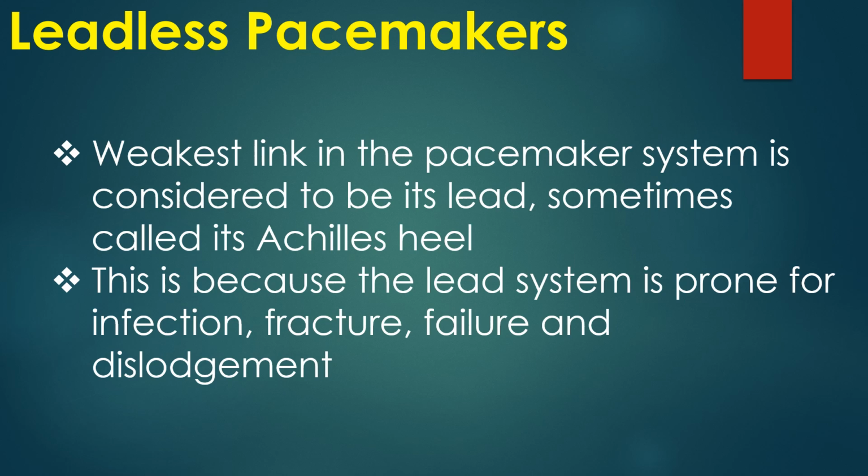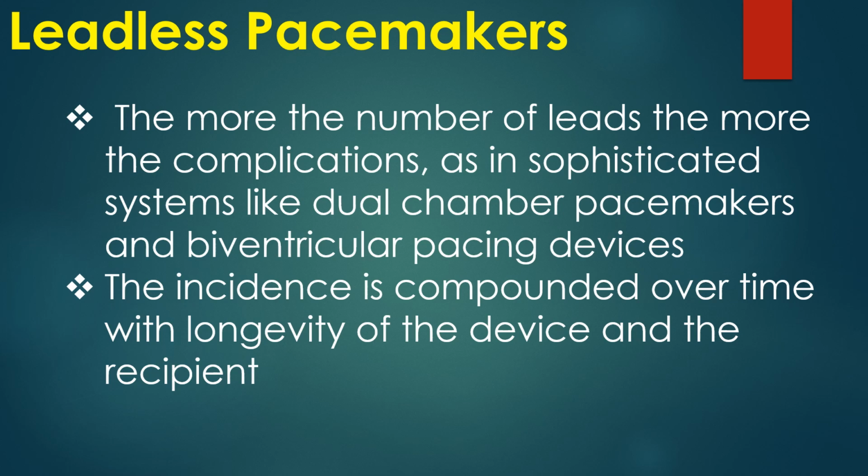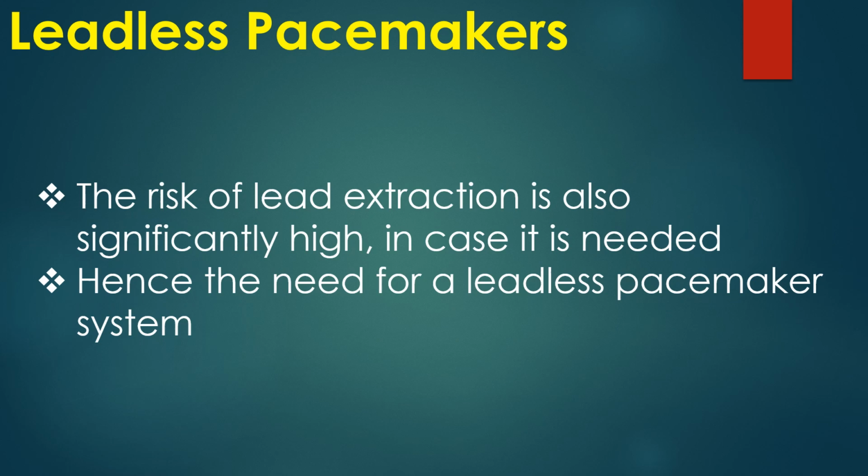Weakest link in the pacemaker system is considered to be its lead, sometimes called its Achilles heel. This is because the lead system is prone for infection, fracture, failure and dislodgement. The more the number of the leads, the more the complications, as in sophisticated systems like dual chamber pacemakers and biventricular pacing devices. The incidence is compounded over time with longevity of the device and the recipient.